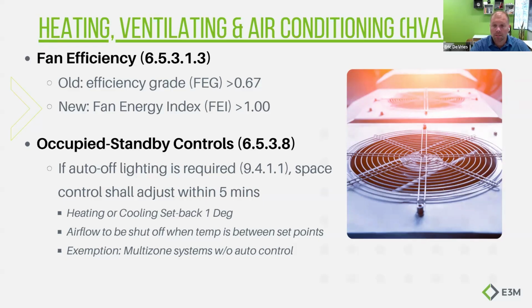This seems like a lot of cost. This seems like a lot of headache in coordination and integration between electrical and mechanical contractors to save 1 degree. The reason that this exists, and the reason that the state chose to adopt it, is because the next code edition doesn't make it 1 degree, it makes it 3 degrees. This is an incremental step that they're trying to use the lighting occupancy sensor to take. My office here is, I'm not a VAV system, but let's say I was, right? Let's say I had my own zone of temperature control here. They're trying to make sure my office isn't overly heated or overly cooled if I've gone to attend a meeting and I've been gone all day. So that is what this requires.